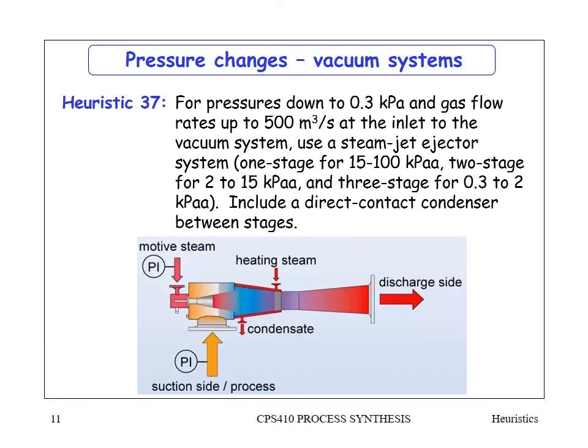For pressures down to 0.3 kPa — about the lowest you'd expect to go — and gas flow rates up to 500 cubic meters per second (about 100 times more than liquid ring vacuum pumps), use a steam jet ejector system. A three-stage system is needed to reach 0.3 kPa; two stages for 2–15 kPa; and one stage for 15–100 kPa absolute. A direct-contact condenser between stages sprays water to condense the steam. A diagram of a three-stage ejector system will be shown on the next page.